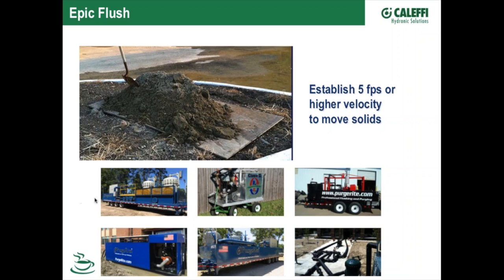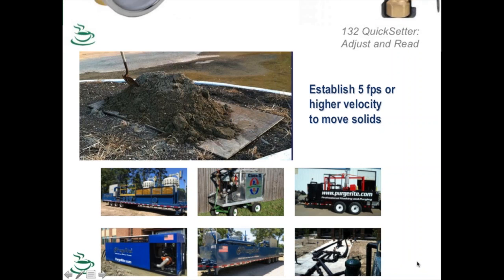We do offer one of those. Caleffi, we've got a little 1/2 horsepower fill and purge cart that can sometimes help you, and sometimes you need to call in the big boys like this here. They can purge up to a 48-inch pipe size with this equipment here that they put together. So make sure that you're getting that debris out, that you're purging it.